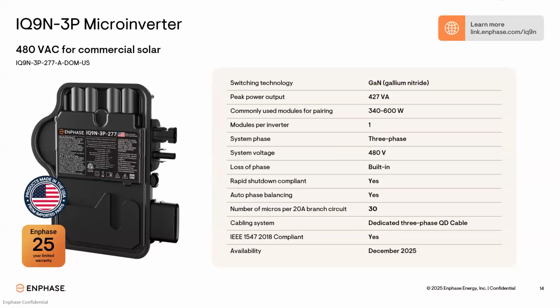So the IQ9N 3P 277, 480 volt, does operate on 480 volts, has a peak power output of 427 volt amps, and is commonly paired with modules from 340 to 600. But be sure to always utilize the module compatibility calculator on the website to verify your module will accurately pair with that microinverter.